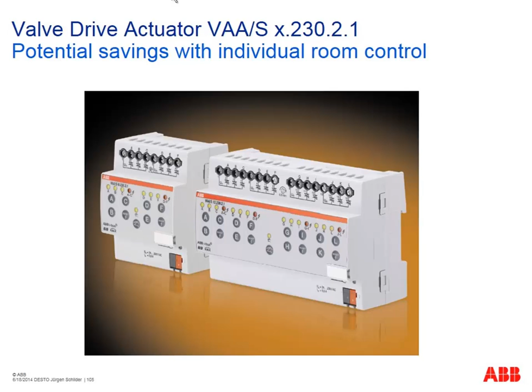Different from this, we have a further electronic output called valve drive actuator. Very similar, but there are some differences you should know. Again, the application not really different. Room temperature control together with the room thermostat and our valve drive actuator controlling thermoelectric valve drives, but no motorized valve drives. Not possible here. So that's one big difference. Only electrothermal valve drives can be connected here for temperature control. So one difference.